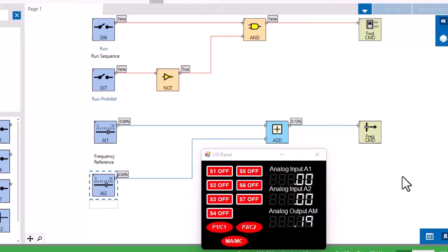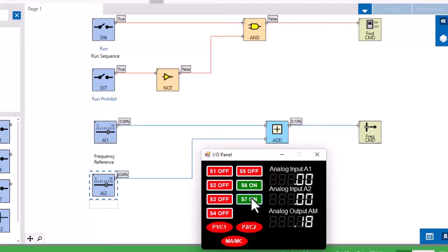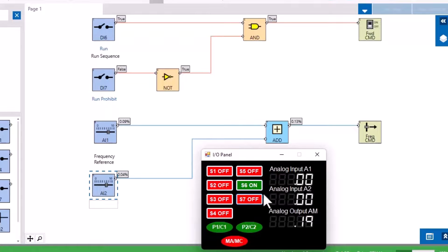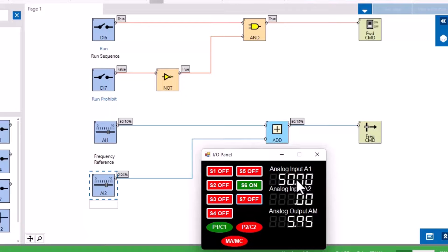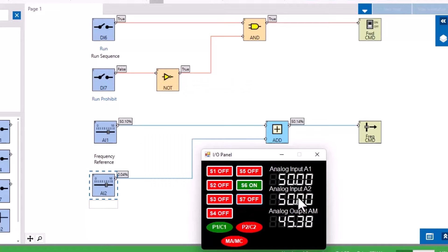I'm going to use the virtual I/O and the monitoring function in DriveWorks EZ to verify the program is working correctly. I can see that the drive will only run if terminal S6 is closed and S7, our run prohibit, is open, just as the customer requested. If I set A1 and A2 at 50% each, then they do add together I have 100% or 60Hz as my frequency reference.